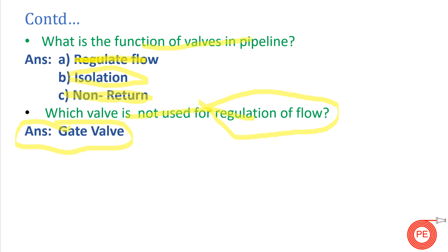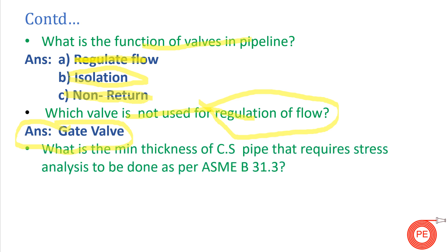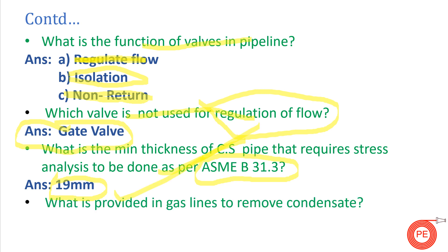What is the minimum thickness of a CS pipe that requires stress analysis to be done as per ASME B31.3? If you refer to ASME B31.3, the thickness mentioned is 19 mm. So if the wall thickness is greater than 19 mm, it must be considered under stress analysis.